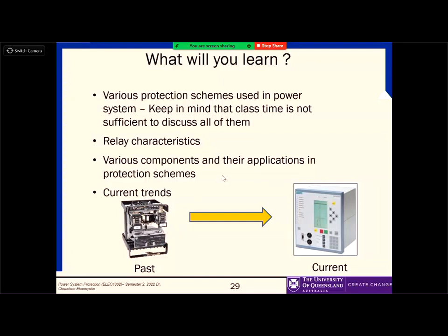What they have done is implement those same conditions in a digital relay — that's a software code, written to identify the same conditions. In the old relay, everything happens mechanically. Those are the major changes, and the digital ones are probably more accurate, but some of the old ones are still working after 50 years.